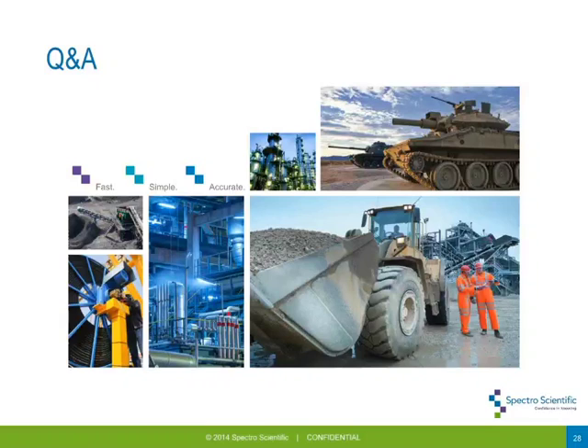Question: Just how portable are these units? Are some of them battery powered? Yes — many of these systems are battery powered, with rechargeable batteries already installed. You can operate them with a power supply connected, or disconnect and walk around to the specific area where your equipment is operating. Many of these tools are battery operated. Specifically for engine applications, the FluidScan, the fuel dilution meter, and the viscometer are all battery operated. For things like the particle counter, that's still more of a benchtop tool and is powered by mains.